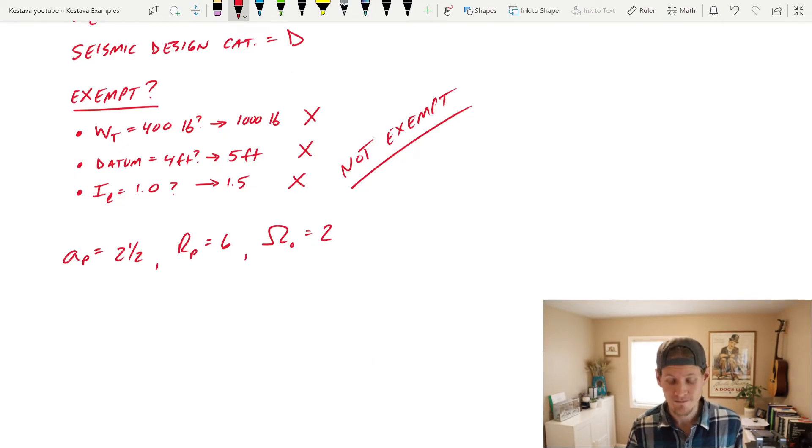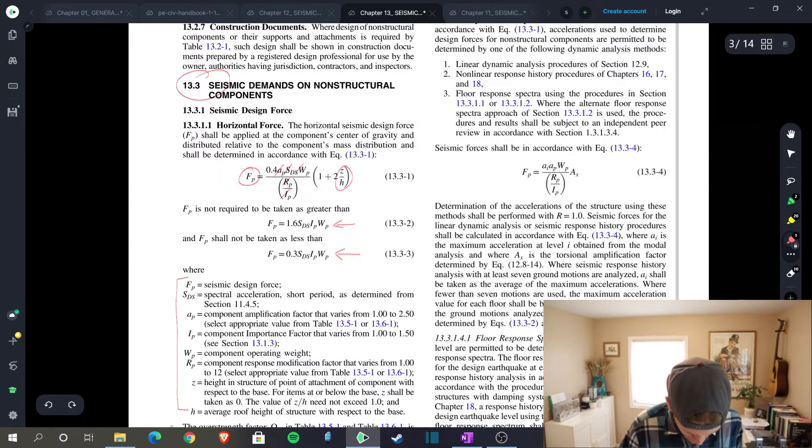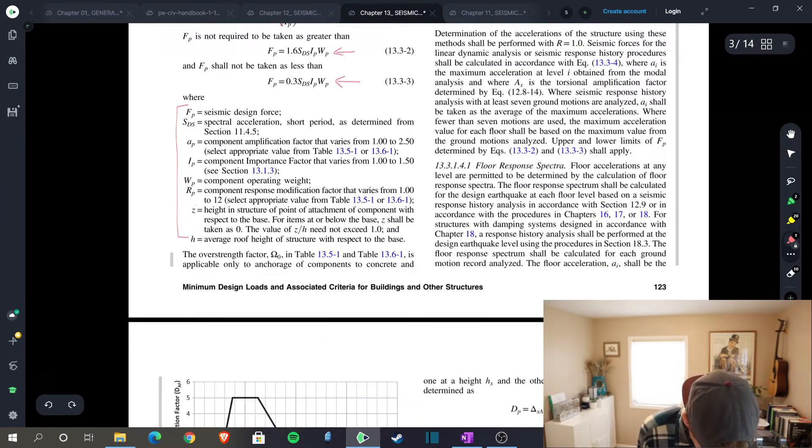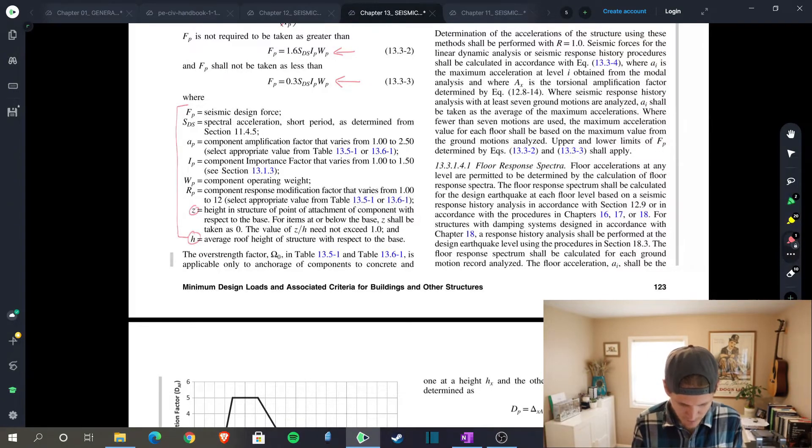Let's see what else we need in our equation. Well, it's cool because we have everything else besides Z and H. And if we scroll down, Z and H are given right here. Z is the height in structure of point of attachment of component with respect to the base. Z over H need not be taken greater than 1.0. And if your unit is located on the ground floor of something, then Z over H is just zero. And then H is defined as the average roof height of the structure with respect to the base. What does all that quite mean?